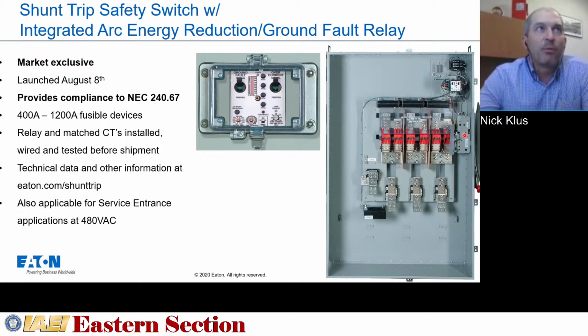One of the things we're proud of, we do have that. You can see to the right, from anything from a 400 to 1200 amp design, and we sell that as a standalone shunt trip safety switch design. So even if you have an application where it's not necessarily needed to have arc energy reduction or ground fault, you can buy a remotely trippable safety switch from us.